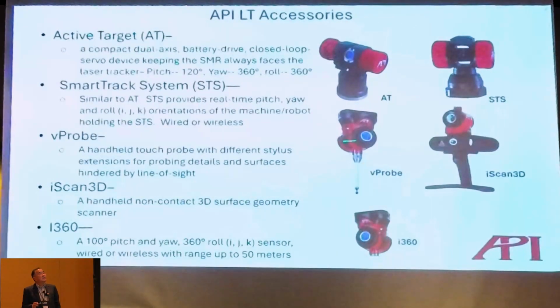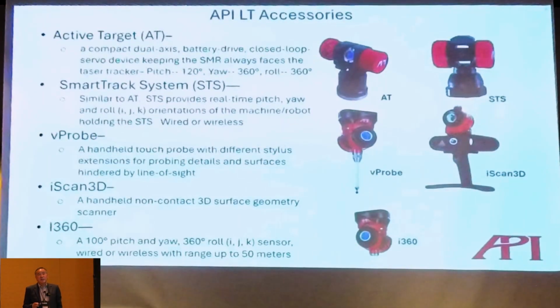A V-probe is basically a handheld probe, where we have a stylus. The ruby tip here is where the measurement occurs. So the laser beam tracks here with a very wide angle acceptance and 360-degree roll capability. So it always maintains the final measurement at the tool tip. It's almost like a CMM. So it allows you to measure the detailed features and at the same time to avoid the problem of the line of sight.